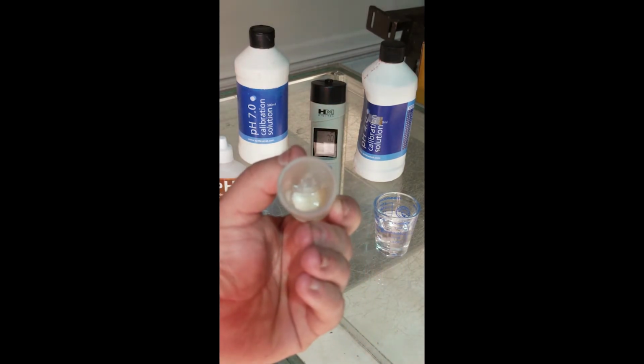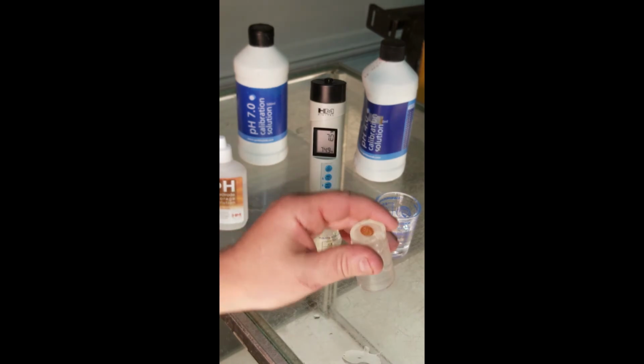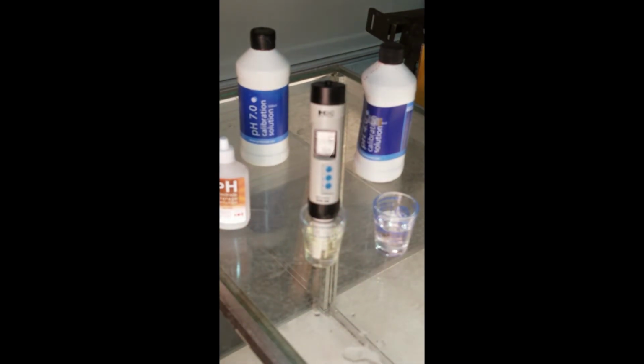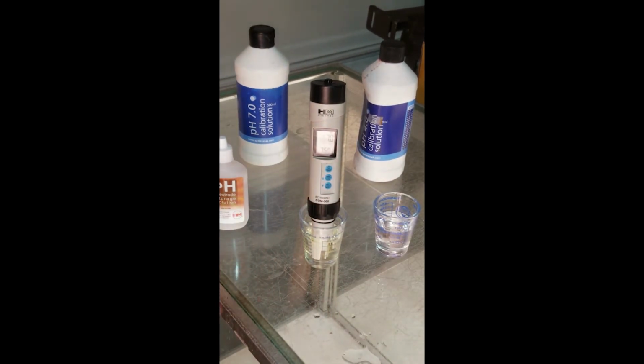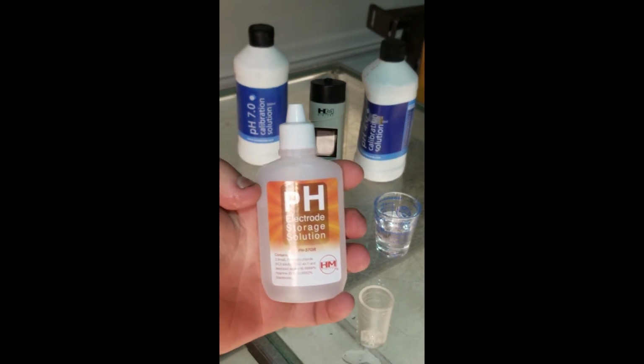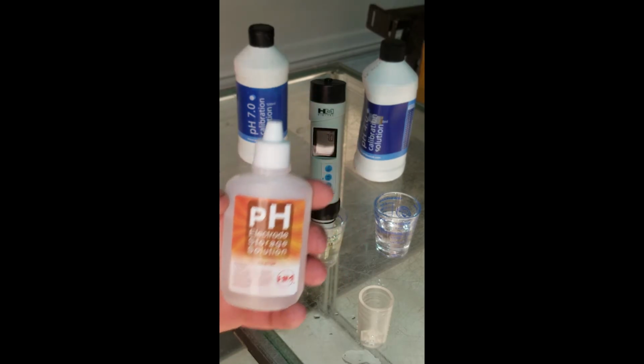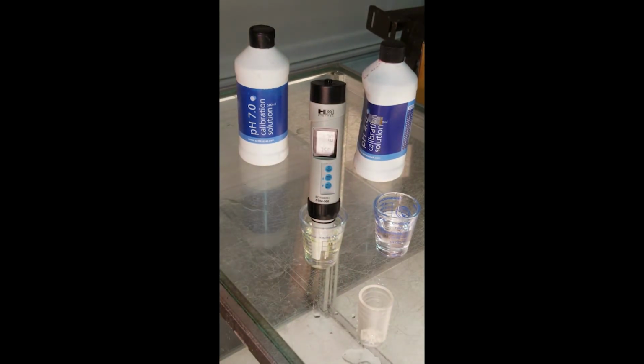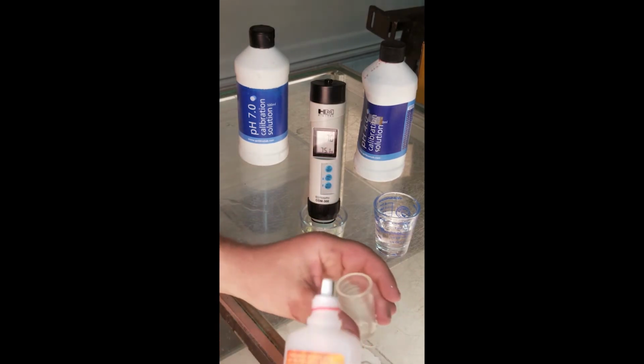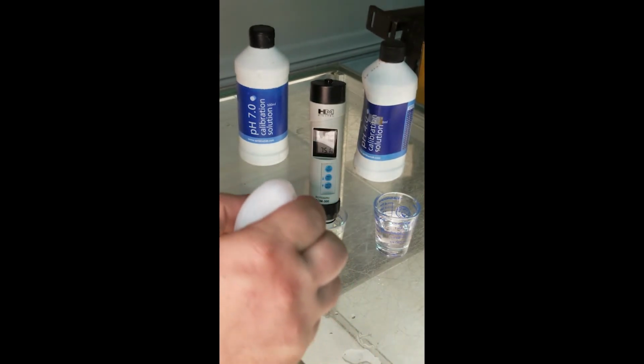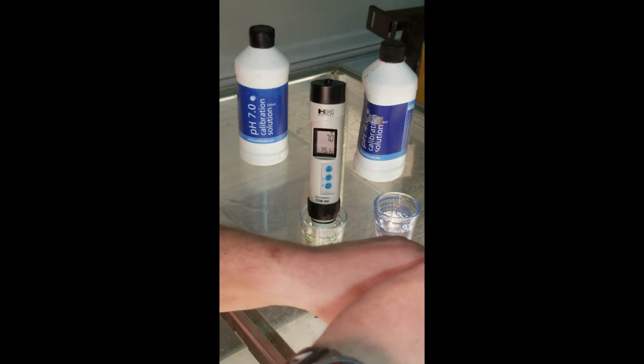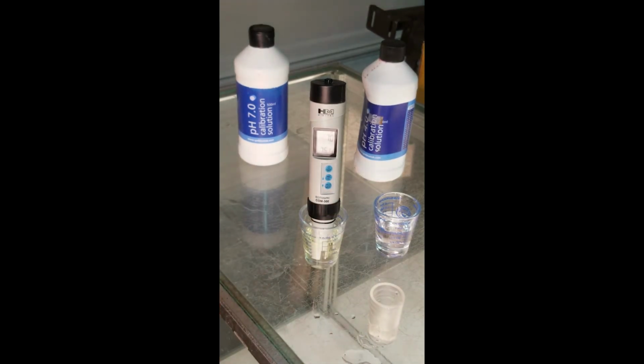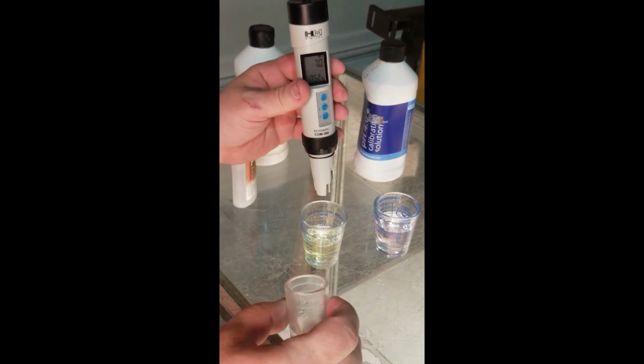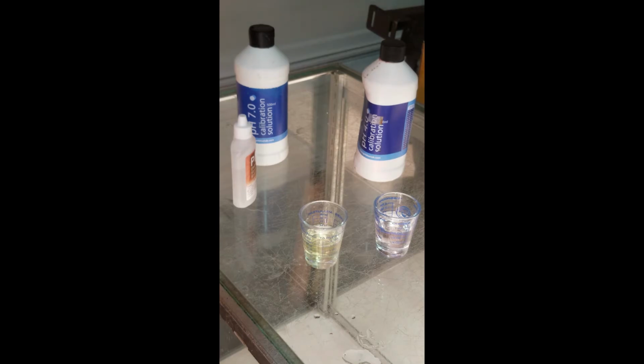So what I'm going to do here, as you notice, there's this little sponge in the bottom. I'm going to see if I can get that out. It doesn't really matter. I can stick my finger in there and kind of squeeze the moisture that's in there. And always store in an electrode storage solution. This is basically deionized water and salt. So it's basically like a saline solution. It's a very high ppm, but it causes the pH meters to have such a high ppm and a specific pH that they don't tend to walk on you and go out of calibration so easily.